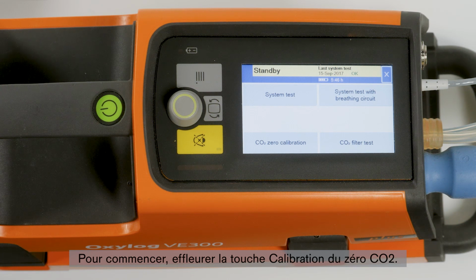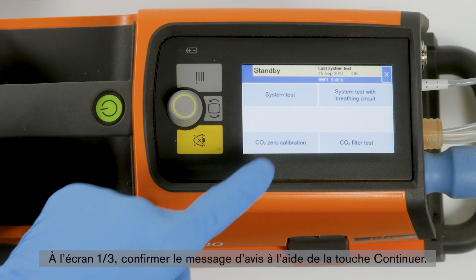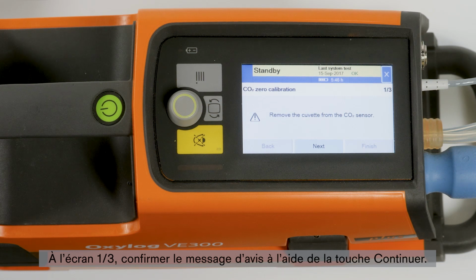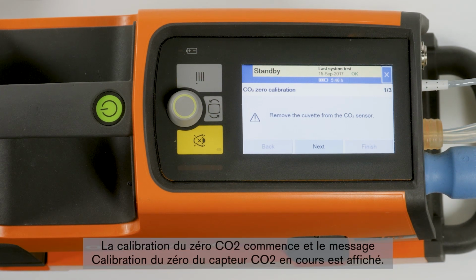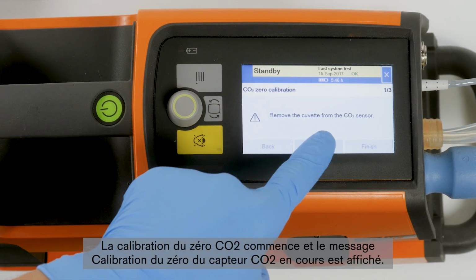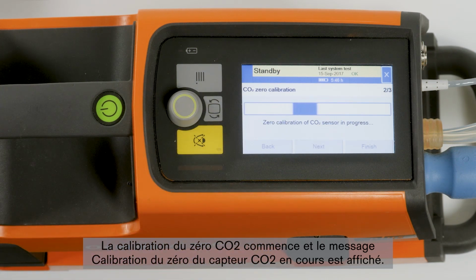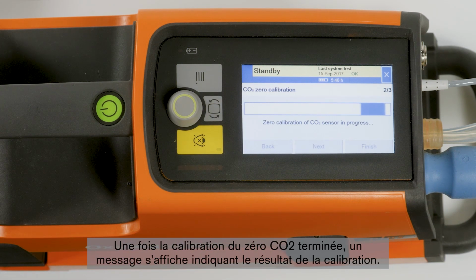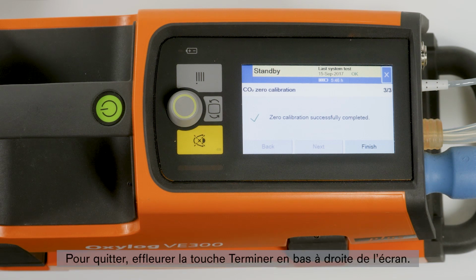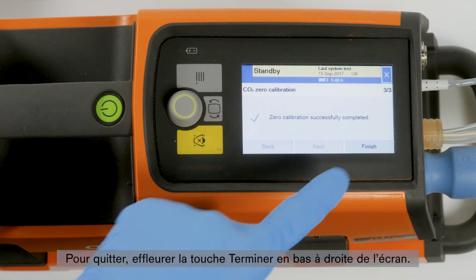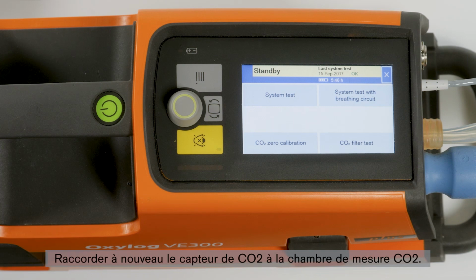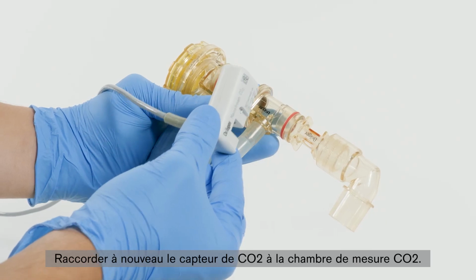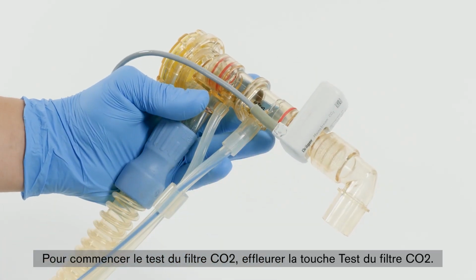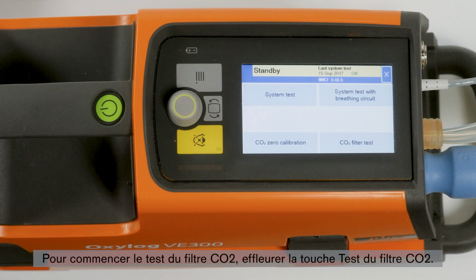To start the CO2 zero calibration, touch the button CO2 zero calibration. On screen 1 out of 3, confirm the advisory message with the next button. The CO2 zero calibration starts and the message Zero calibration of CO2 sensor in progress is displayed. When the CO2 zero calibration is completed, a message is displayed indicating the result of the calibration. To exit, touch the Finish button in the bottom right-hand corner of the screen. Reconnect the CO2 sensor to the CO2 cuvette.